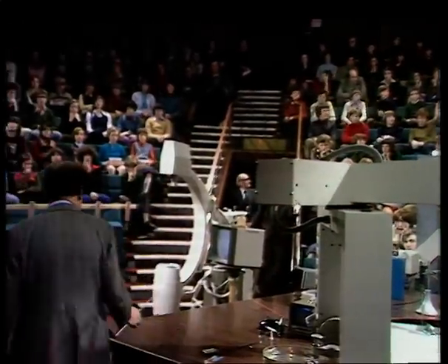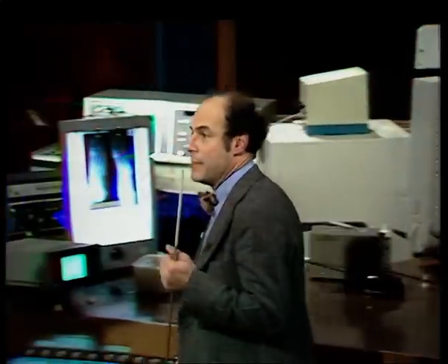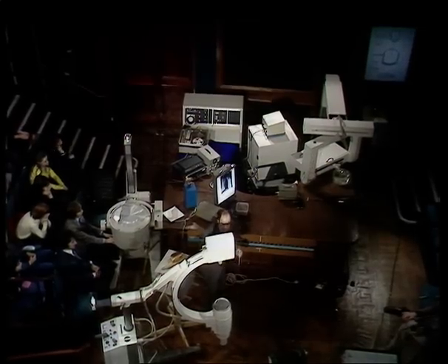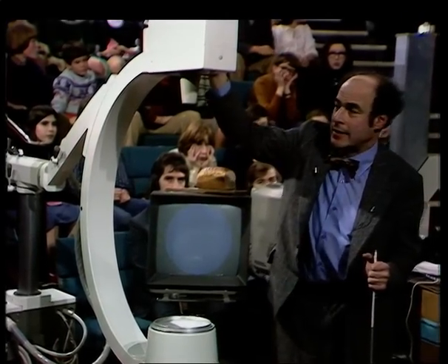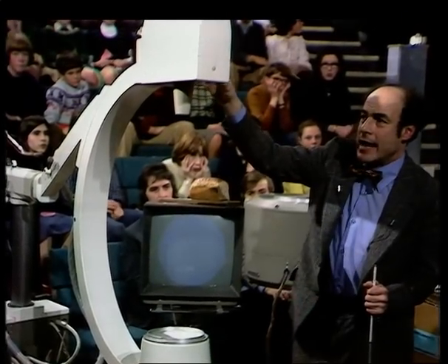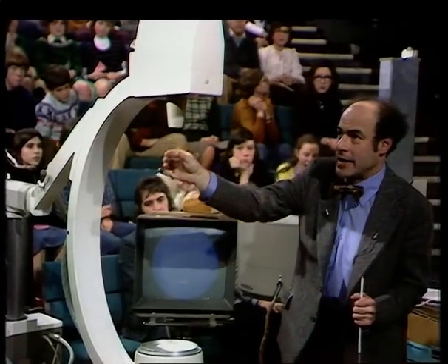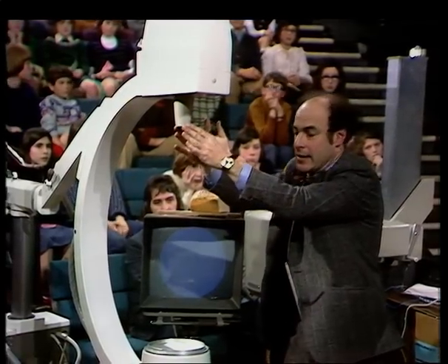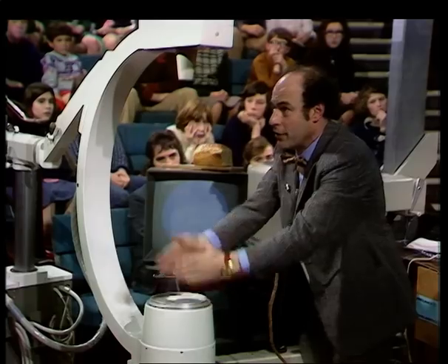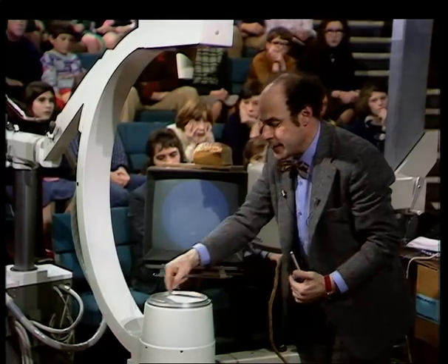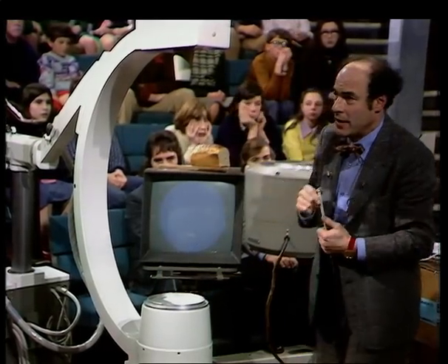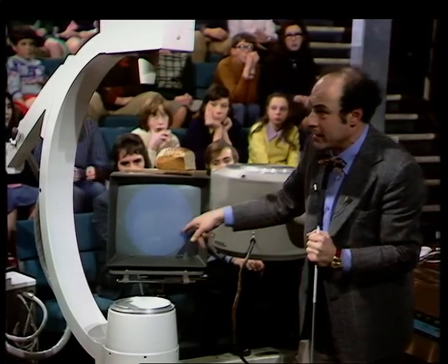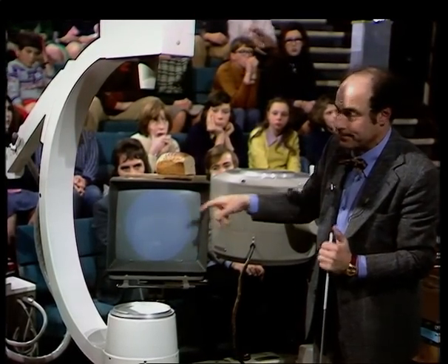Well, we have got one of these image intensifier machines here. And just to point out the major parts to you, the X-ray tube is inside here. It's surrounded by lead and other shielding, so that the beam of X-rays comes out of here. And the beam of X-rays is very accurately defined indeed, so that the whole cone of X-rays falls within this plate here, which is the front surface of the image intensifier, which I've told you about. And here is a television monitor on which the picture appears.